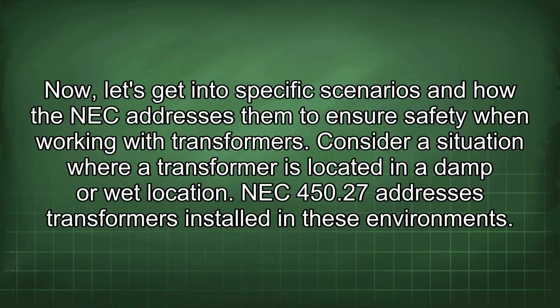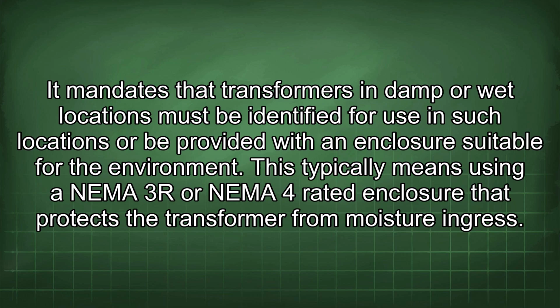Now, let's get into specific scenarios and how the NEC addresses them to ensure safety when working with transformers. Consider a situation where a transformer is located in a damp or wet location. NEC 450.27 addresses transformers installed in these environments. It mandates that transformers in damp or wet locations must be identified for use in such locations or be provided with an enclosure suitable for the environment.